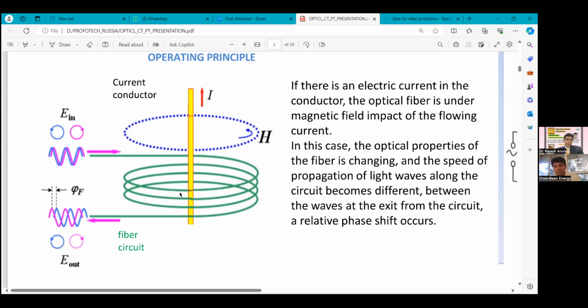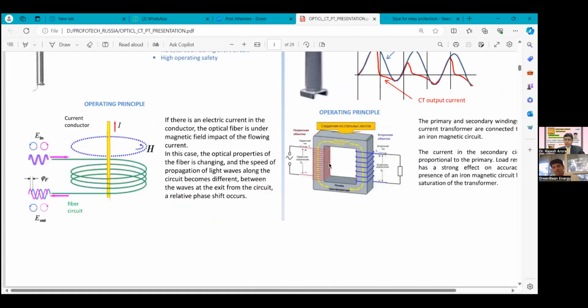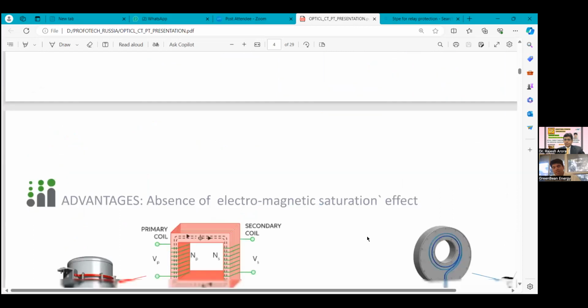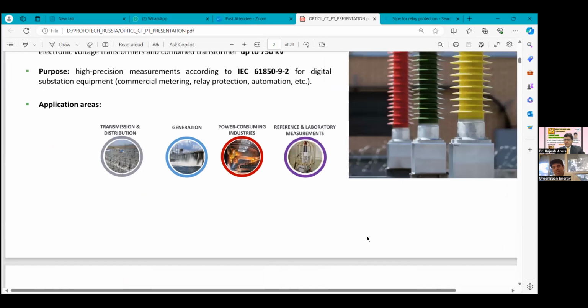Tell me one more thing. Suppose I have to go for procurement of that optical CT. There should be some IEC codes and type tested material, and how to ensure that? Do you have any relevant IEC code applicable for that optical CT? I know about the testing methodology and other things. As per the IEC, the data streaming is according to IEC 61850. But for testing, I have to check with the company which IEC standard they are performing their tests according to, because without having the material type tested, no one can purchase at a utility, in fact.